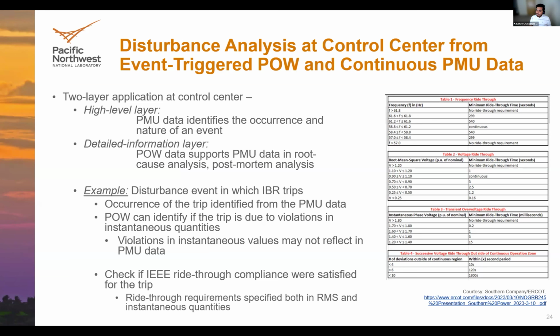Now, the detailed information layer is where we use the point-on-wave data to complement PMU data in the root cause analysis of the event. So this is where basically the postmortem analysis is happening. You get the detailed signature from the waveforms and try to understand what led to that IBR trip, or what were the preceding signatures that finally led to the IBR trip. So one example that I put here is a disturbance event in which an IBR trips.